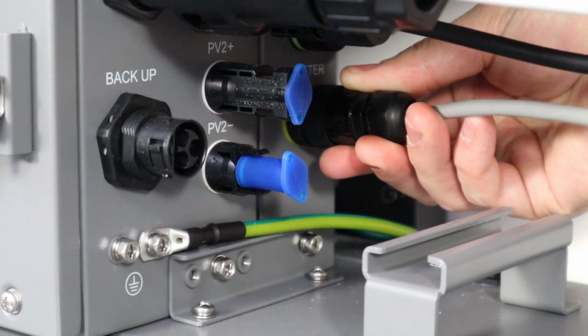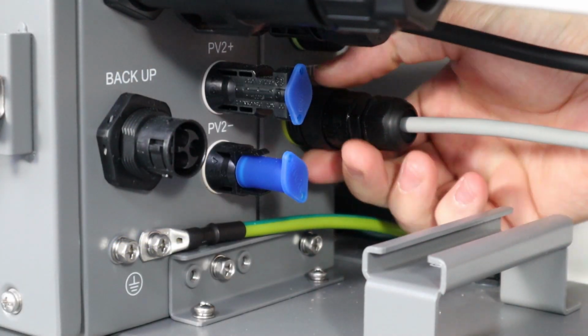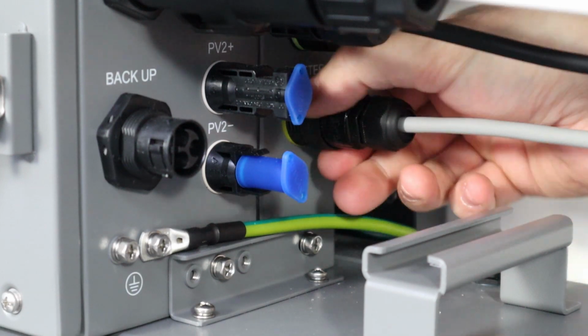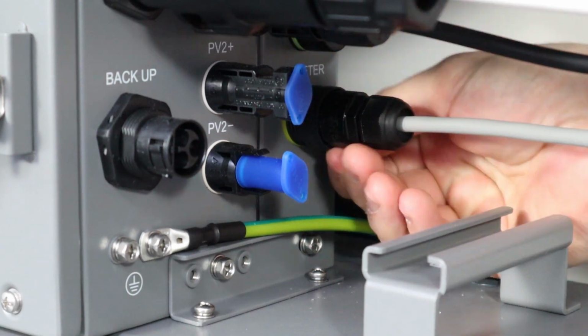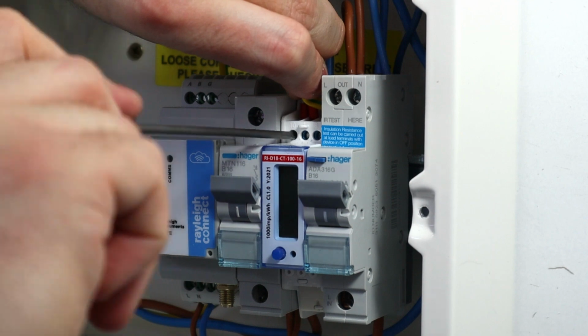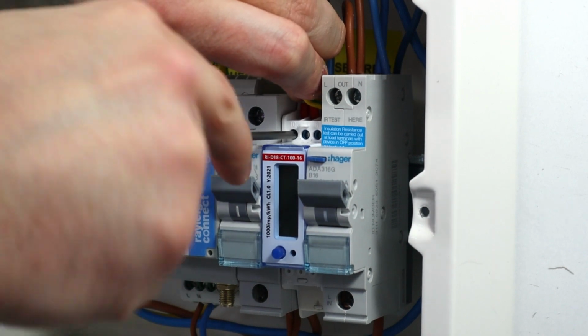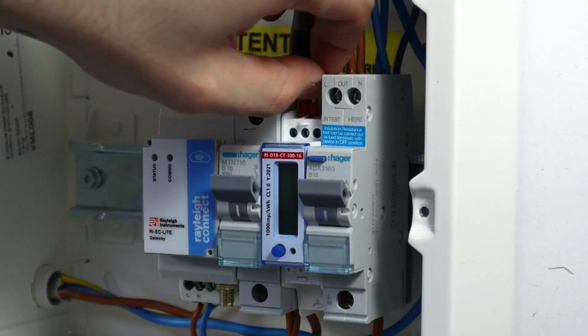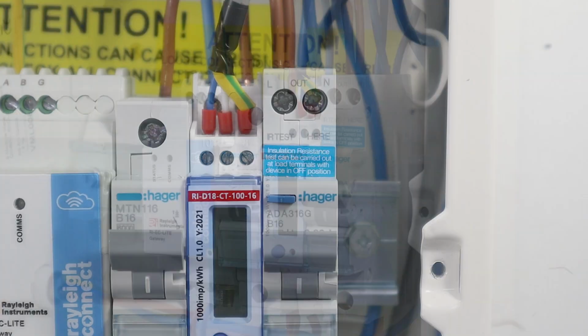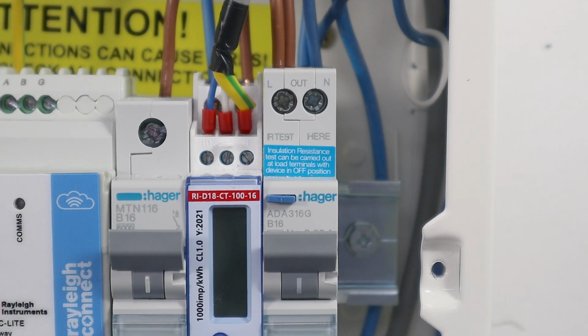We recommend the use of Belden 9841 shielded twisted pair cabling, or equivalent, for all your Modbus connections. The other end of this connection should be to the Modbus terminals of a suitable energy meter. In this scenario, the meter calculates the house load and sends the information via Modbus to the inverter for the inverter to control discharge from the battery. Note that the Modbus connection should only be earthed at one end.